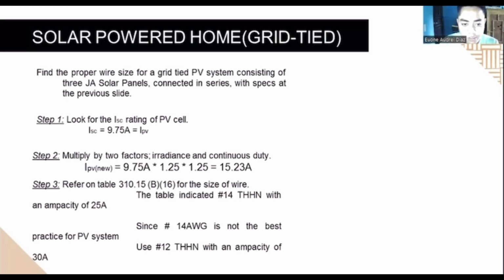Step 2. Multiply by two factors, 125% and the continuous duty. IPV is equal to 9.75 amps multiplied by 1.25 multiplied by 1.25, which is equal to 15.23 amps. Step 3. Refer to the table 310.15 B 16 for the size of wire. The table indicates number 14 THHN, thermoplastic high heat resistant nylon coated, with an ampacity of 25 amps. Since number 14 AWG is not the best practice for a PV system, use number 12 THHN with an ampacity of 30 amps.